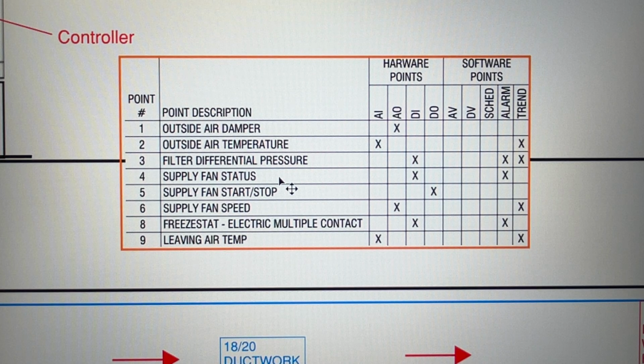You have your supply fan status, which will tell us whether we have power to the supply fan or not. This will be a start-stop function for that same supply fan, so we'll be able to turn it on or off. And then your supply fan speed. This will allow us to determine how much RPM we want to put to the fan based on the CFM that we desire to the space. Then we also have a freeze stat, which will be on the back side, or the discharge side, of the coil. This looks like it's electric, okay, but basically there will be some capillaries on the discharge side of that coil so we can monitor if we have any frost buildup, etc. Then we also have a leaving air temperature point as well.